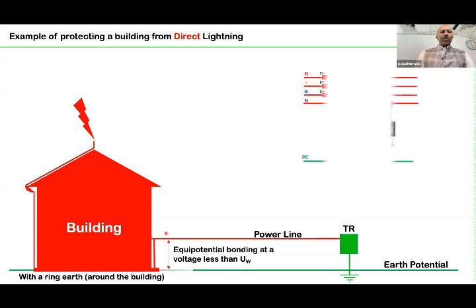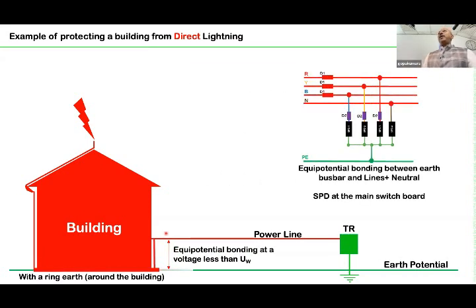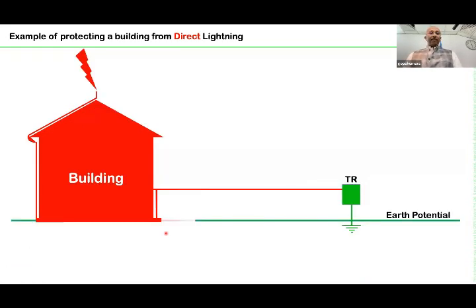So let me skip. What is recommended, or the best practice, is to have an SPD at the service entrance, something like this. This is not a 3+1 connection. We call it 4+0. This 0 has got no value. There are 4 SPDs between each of the current carrying conductors and earth, as you can see here. So for the service entrance SPD, the best option is to go for a 4+0 SPD, something like this. But of course, challenges are there.